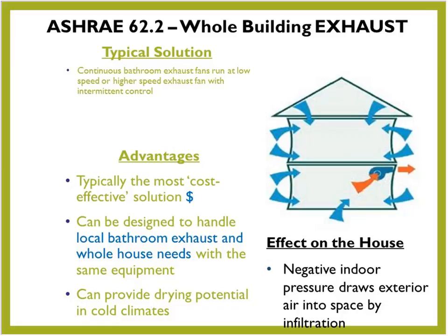And that's actually one of the criticisms of the exhaust ventilation approach, that we don't know where the makeup air is coming from. But certainly, if it's coming from the outside, it's going to be fresher, and that's the most common place for it to come from, when all of the exterior walls are in fact exposed to the outside. So we're bringing in that fresh air by exhausting air that's either high in moisture or just normal indoor air pollutants, and replacing it with fresh air.